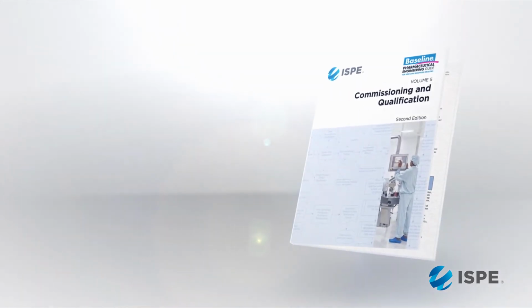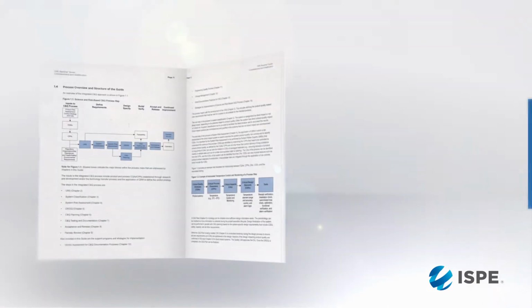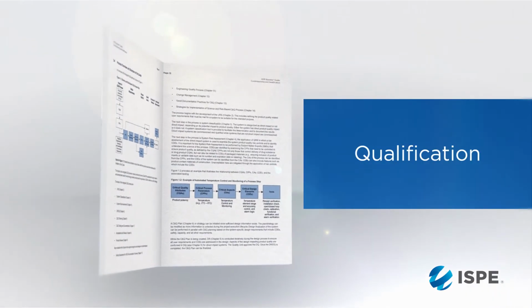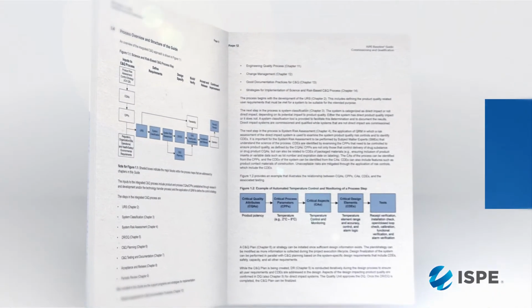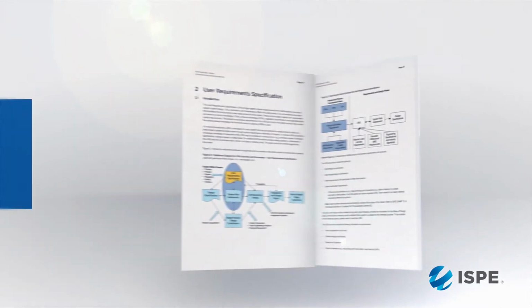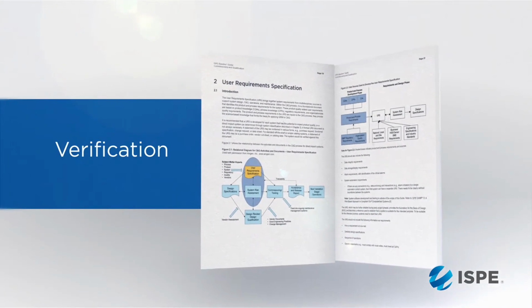If you look at the terms qualification and verification, people sometimes confuse what they mean. In the new ISPE Baseline Guide 5, we've tried to clear up that confusion. When we talk about qualification, we talk about an integrated process where we're doing commissioning and qualification, and the end state is fitness for use, or qualified, at the end of the process. Verification, we define as the process of testing the equipment and documenting the test results that get you to the qualified state at the end of the process.